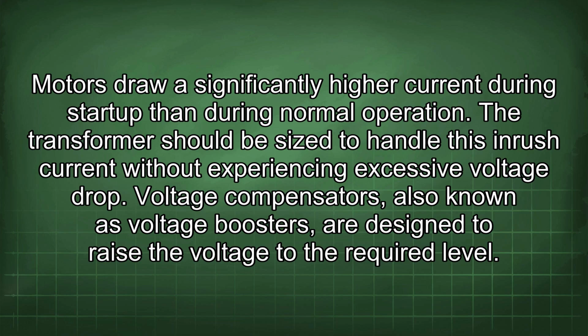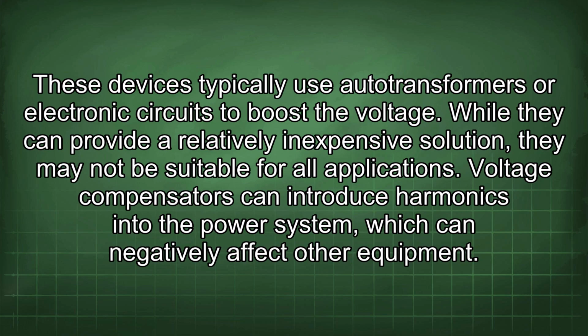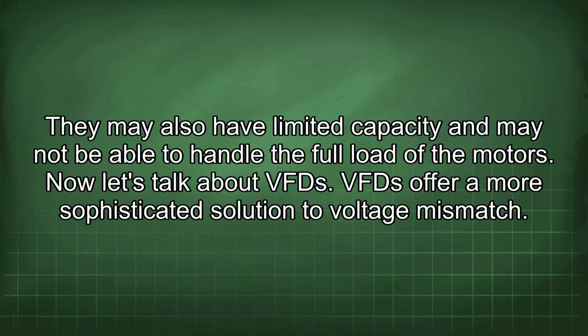Voltage compensators, also known as voltage boosters, are designed to raise the voltage to the required level. These devices typically use auto transformers or electronic circuits to boost the voltage. While they can provide a relatively inexpensive solution, they may not be suitable for all applications. Voltage compensators can introduce harmonics into the power system, which can negatively affect other equipment. They may also have limited capacity and may not be able to handle the full load of the motors.